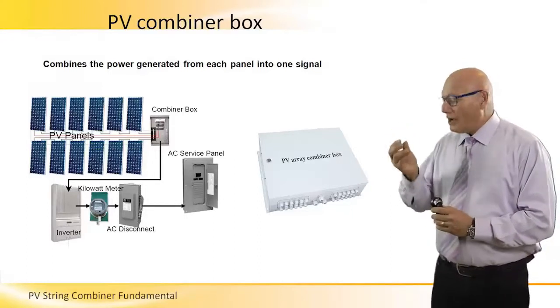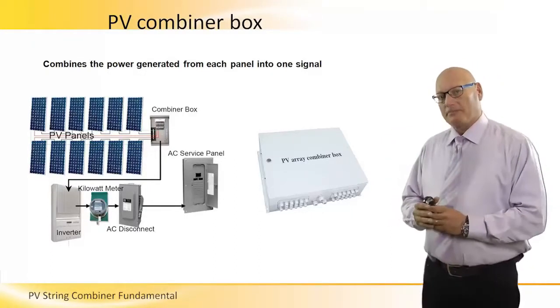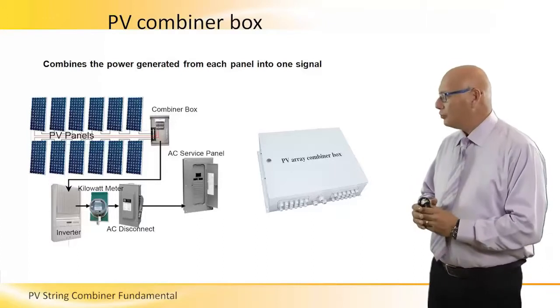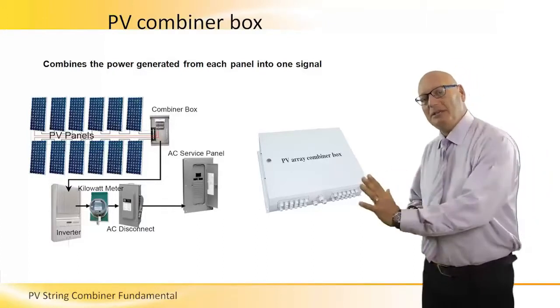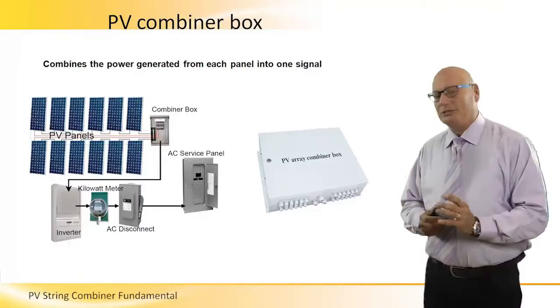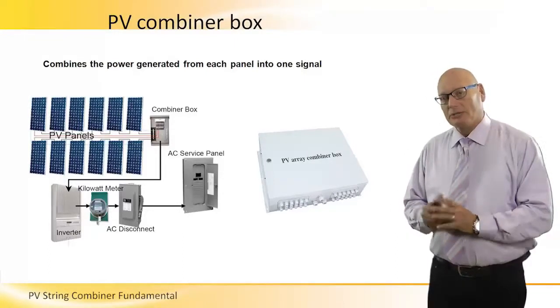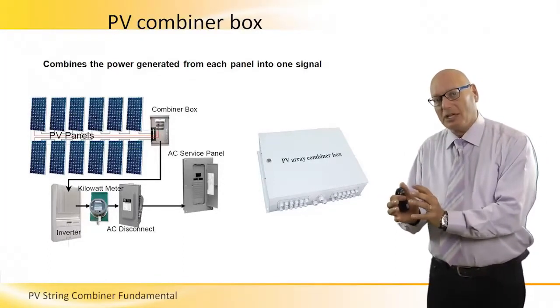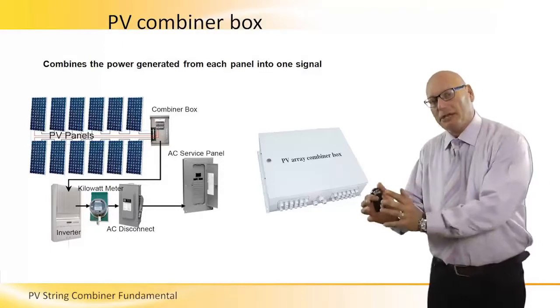The combiner is right next to the panels in order not to have many DC cables running all the way to the inverter. So the combiner combines all the DC cables, the pluses together and the minuses together, and only two cables running to the inverter.